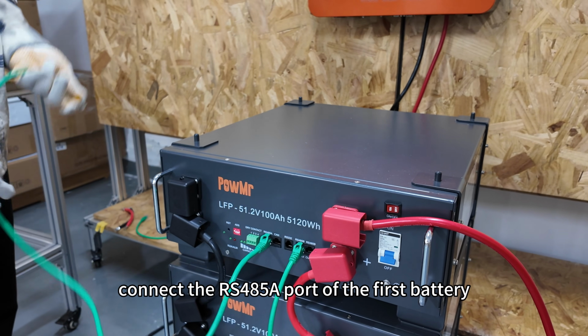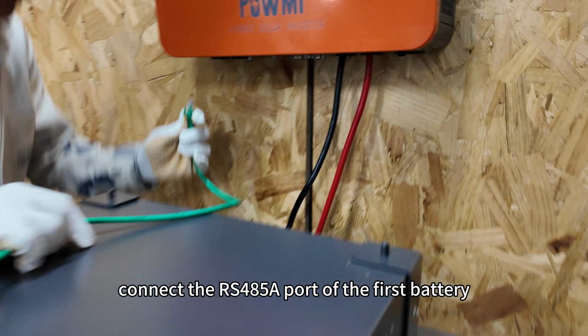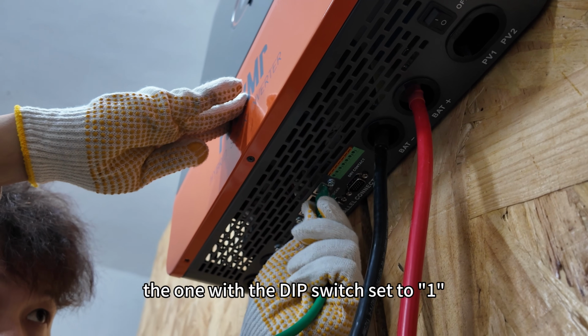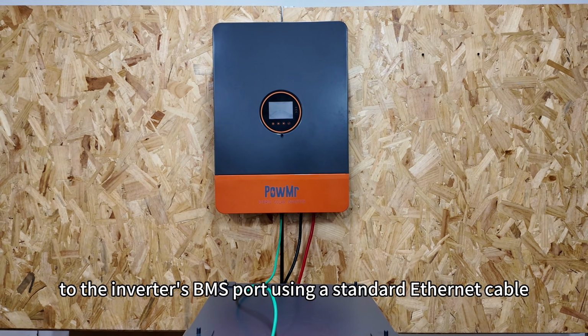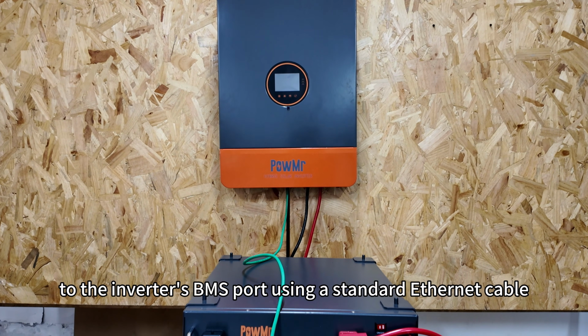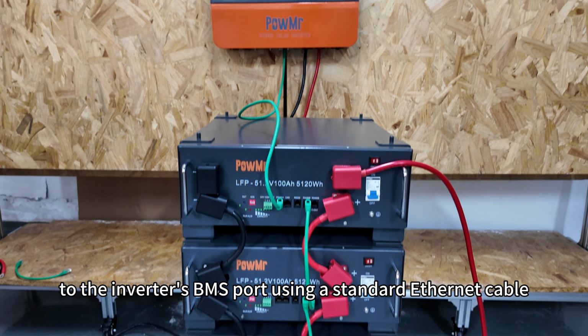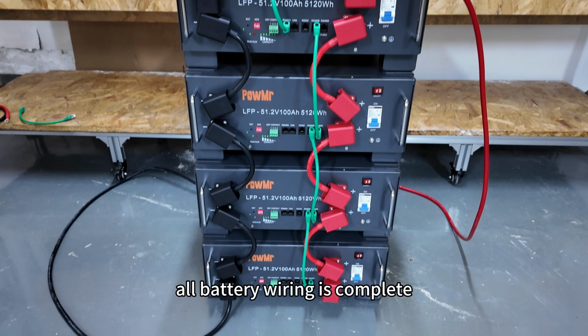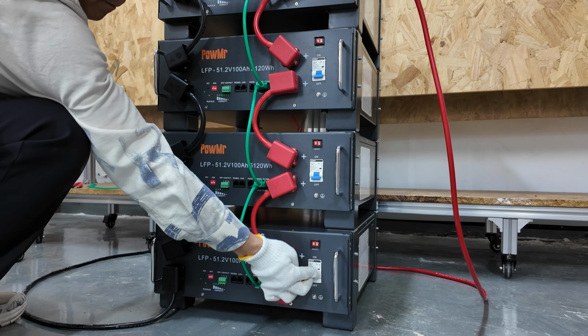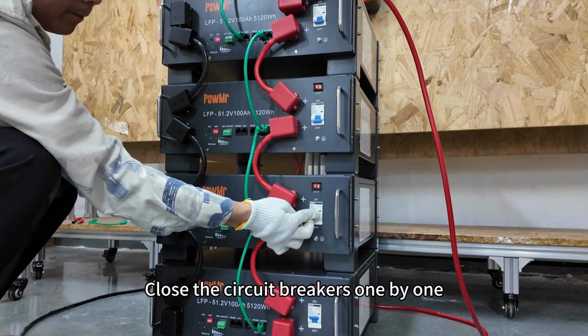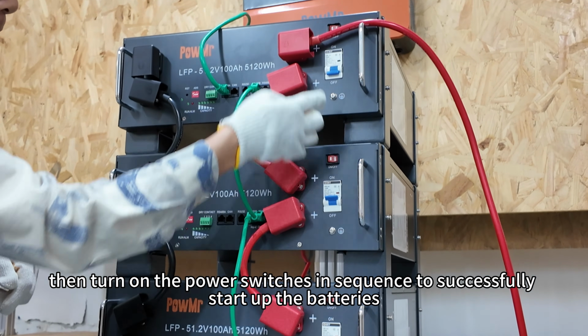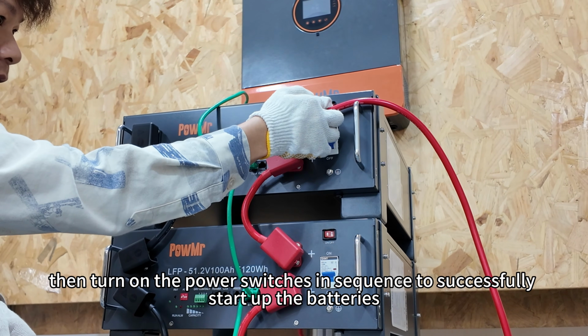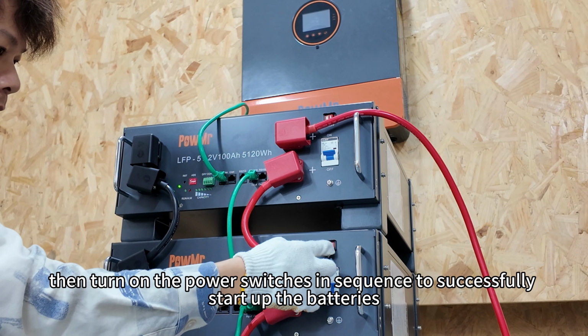Then connect the RS485A port of the first battery, the one with the dip switch set to 1, to the inverter's BMS port using a standard Ethernet cable. At this point, all battery wiring is complete. Close the circuit breakers one by one, then turn on the power switches in sequence to successfully start up the batteries.